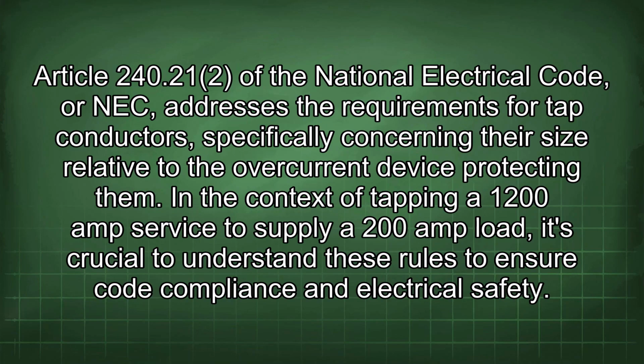Article 240.21 of the National Electrical Code, or NEC, addresses the requirements for tap conductors, specifically concerning their size relative to the overcurrent device protecting them. In the context of tapping a 1200 amp service to supply a 200 amp load, it's crucial to understand these rules to ensure code compliance and electrical safety.